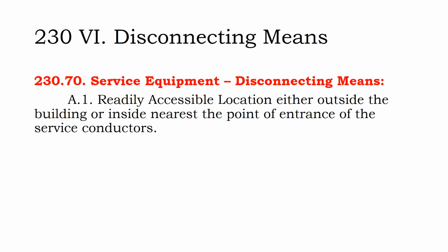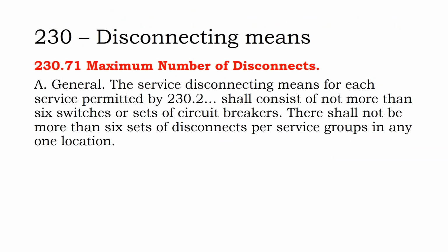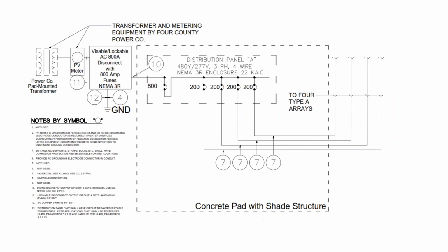Disconnecting means, the same 6-handle rule makes another appearance. So here's an example, this is for a ground mount single line diagram, and we have our main disconnect switch here. We also have another main breaker switch here, so we could put tons of switches along this board if we wanted to, because it's protected by that one main switch. So you could flip one switch and turn everything down the line off.